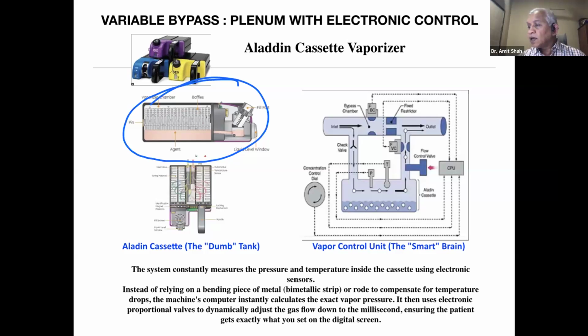Now, how is it different? In our plenum vaporizers, we have to make mechanical things inside, a bimetallic strip or a rod. We have kept wicks. We have increased the surface area. What they are doing inside is measuring the vapor pressure and the temperature, and on the basis of the vapor pressure and temperature available, they are giving this information to their computer to increase or decrease the variable bypass.